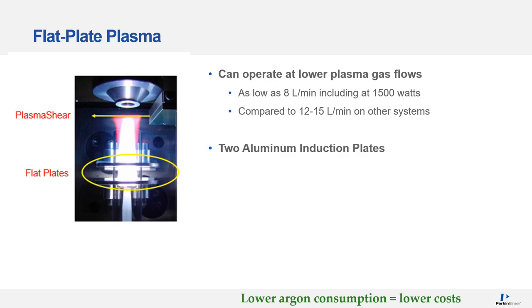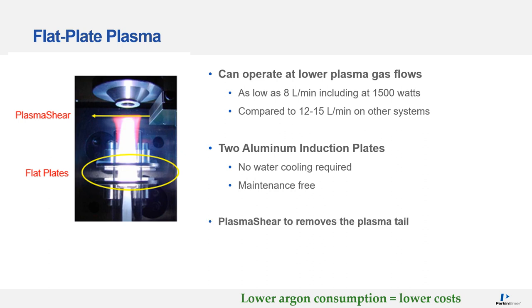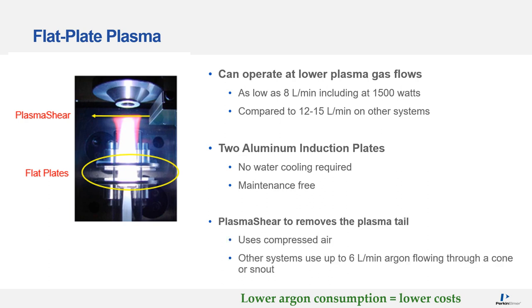The flat plate plasma uses two aluminium induction plates rather than a traditional copper coil. The benefit is that the plates require no water cooling and are maintenance free. The Avio 200 also uses what's called PlasmaShear to remove the plasma tail, and this uses compressed air, compared to other ICPs which can use up to 6 litres per minute of argon flowing through either a cone or a snout to remove the plasma tail.